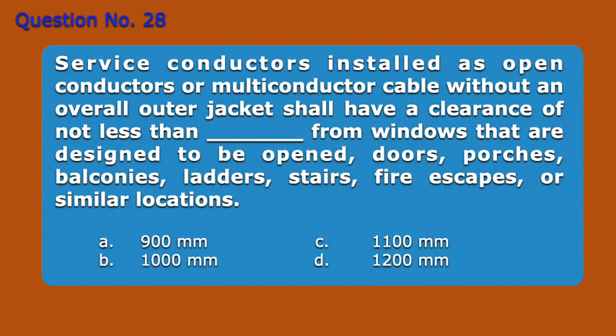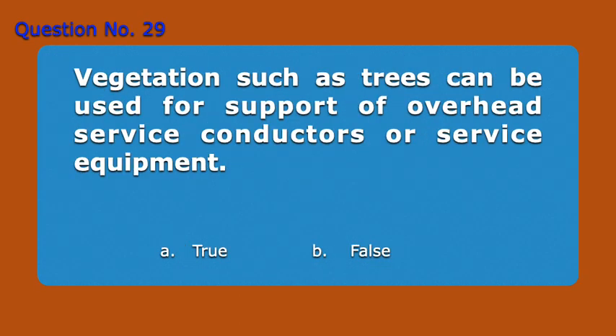Question number 28. Service conductors installed as open conductors, or multi-conductor cable without an overall outer jacket, shall have a clearance of not less than blank from windows that are designed to be opened, doors, porches, balconies, ladders, stairs, fire escapes, or similar locations. A, 900 millimeters. B, 1000 millimeters. C, 1100 millimeters. D, 1200 millimeters. Answer A, 900 millimeters. Question number 29. Vegetation such as trees can be used for support of overhead service conductors or service equipment. A, true. B, false. Answer B, false.